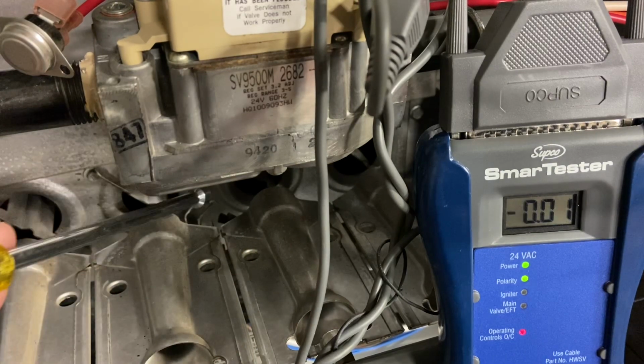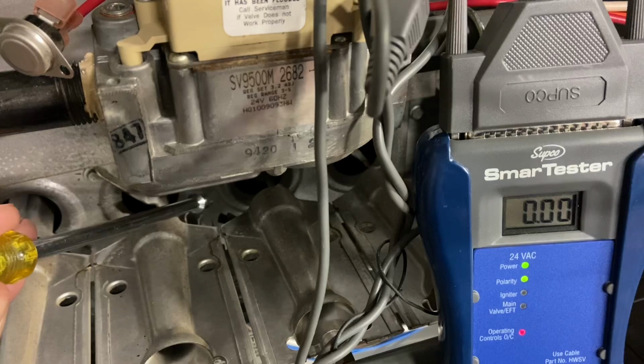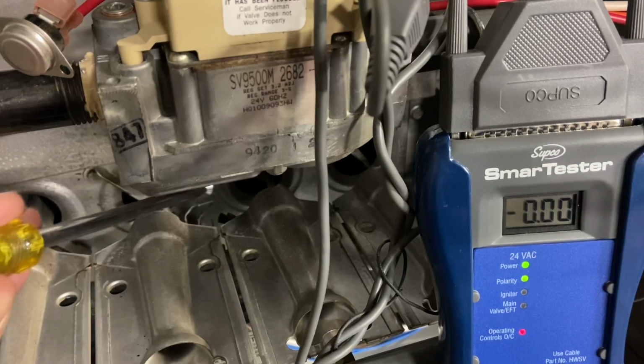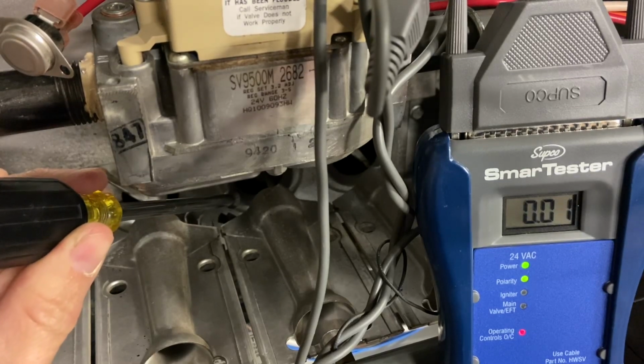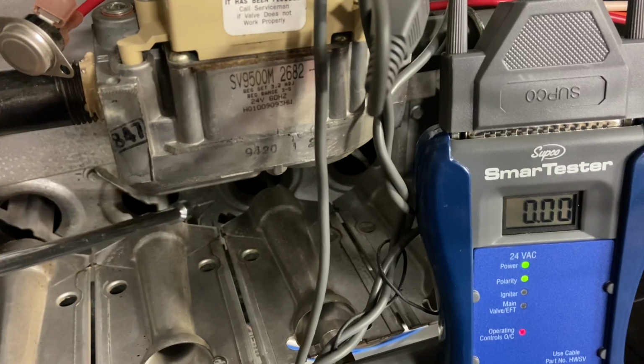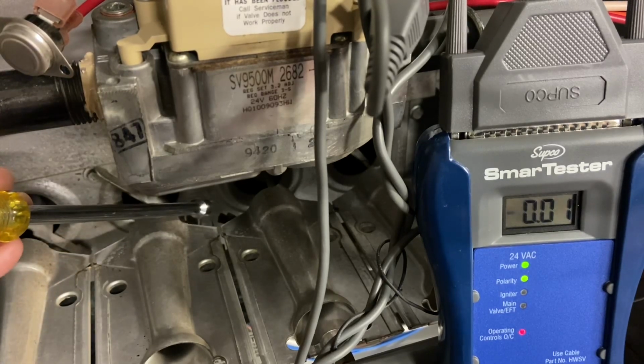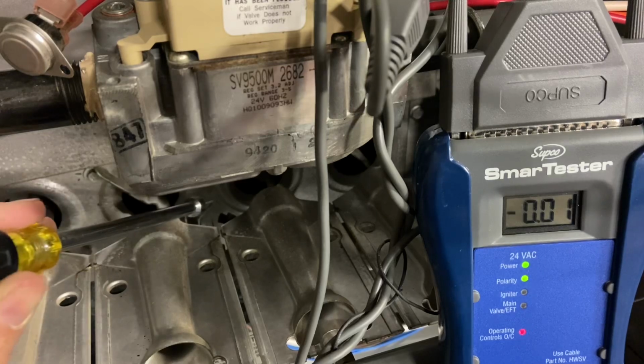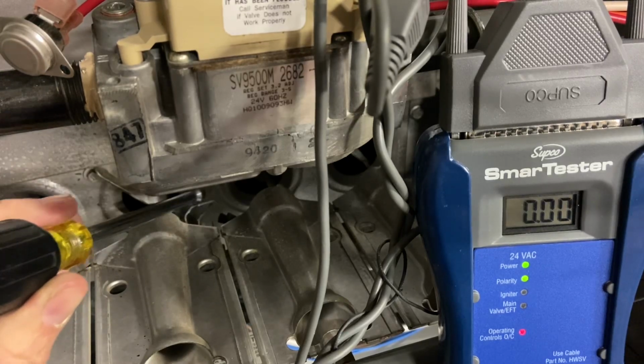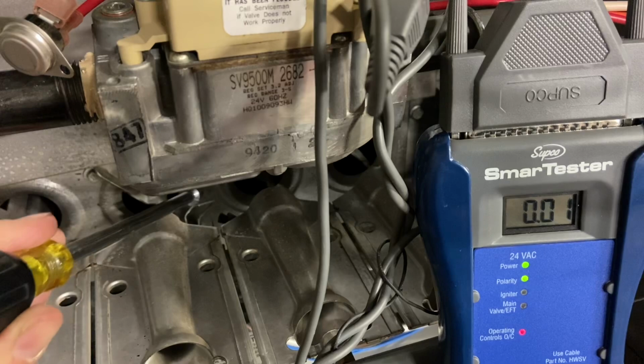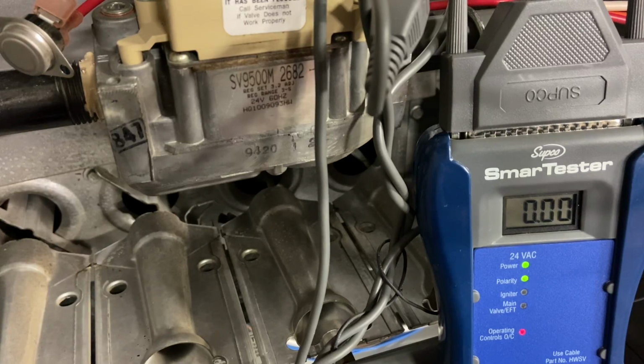Now right inside of here is where we're going to have our intermittent pilot assembly. The pilot assembly that's going to be burning is right here. We also have, which I'm not going to touch, right down low, a little miniature hot surface igniter. Then over here we have a flame sensor, and also the guard, which the flame sensor burns against for the flame rectification.